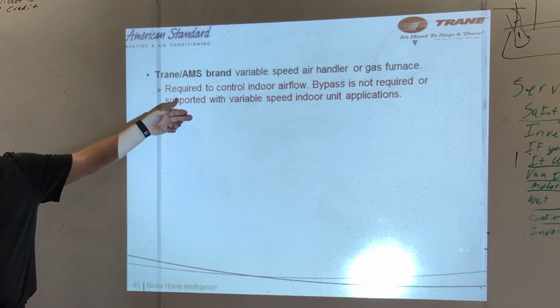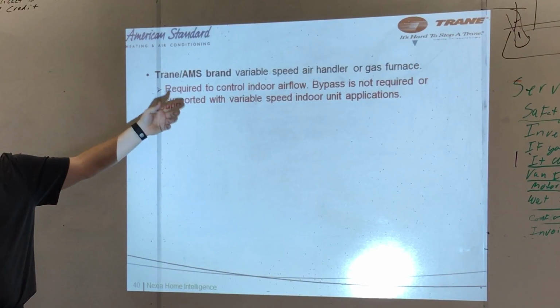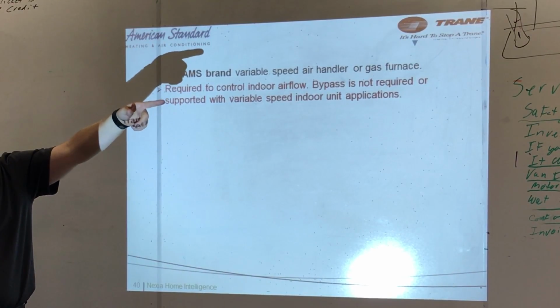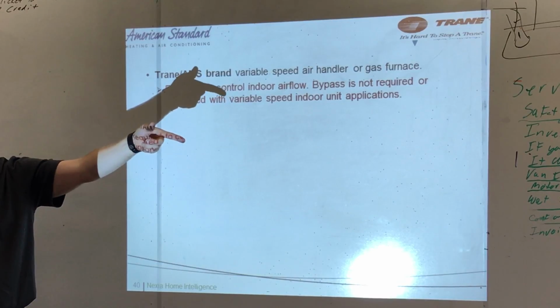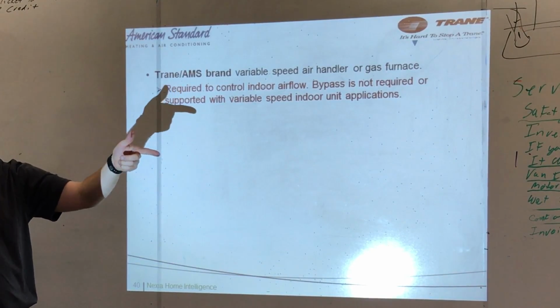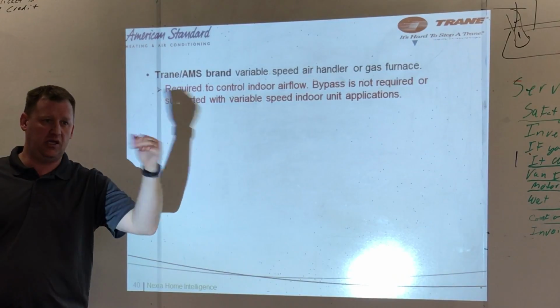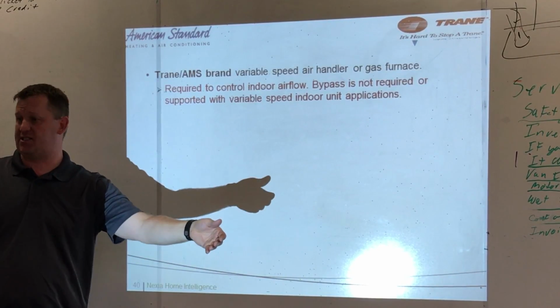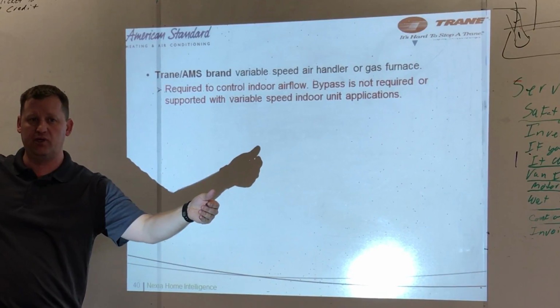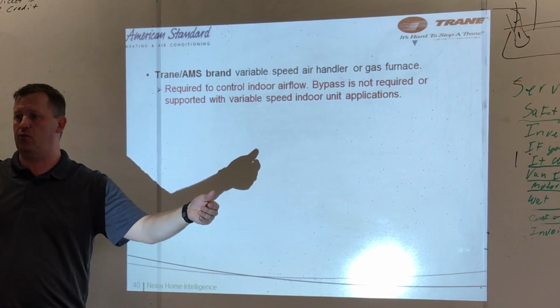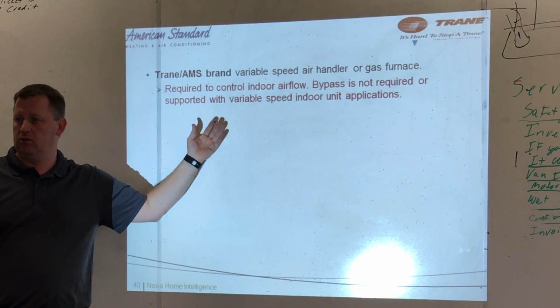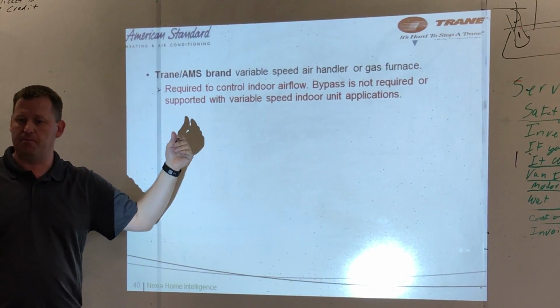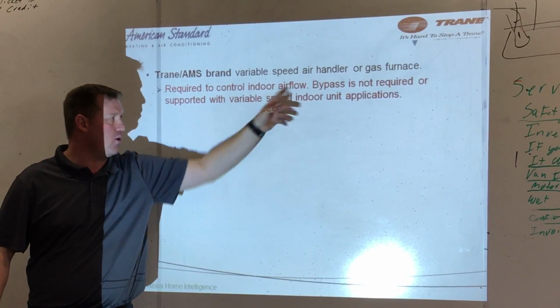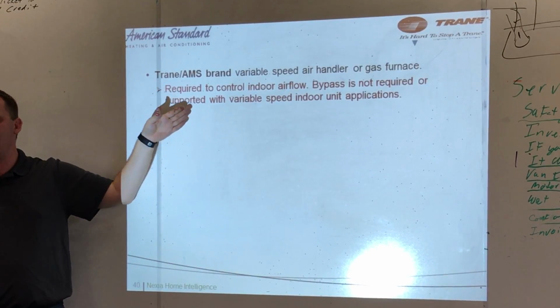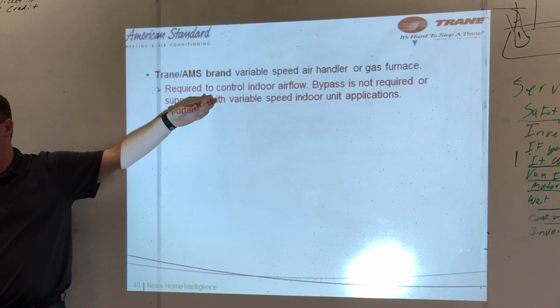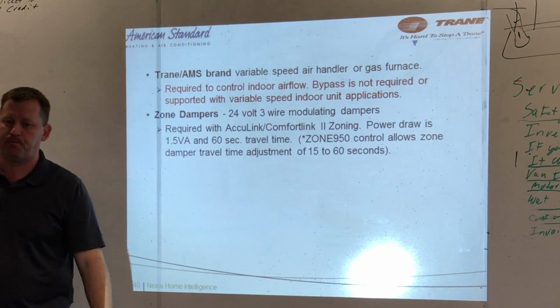You need a variable speed furnace. So watch out for that when you're going out on the old Trane zoning system that didn't require variable speed only. Because you may have some situations where you have a TWE 036C, which is a PSC motor with the zoning system. Because we could do bypass with that one. We could do dump zones. We don't do that with this zone system. Okay? So bypass is not required or supported. You cannot do a bypass with this system. We don't allow it. Okay?